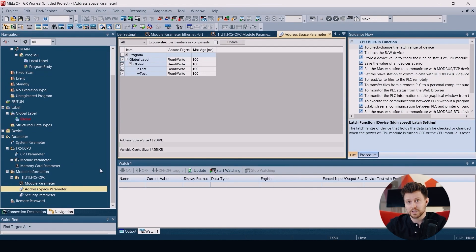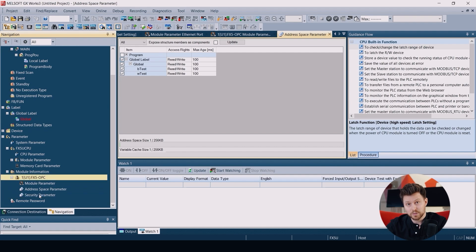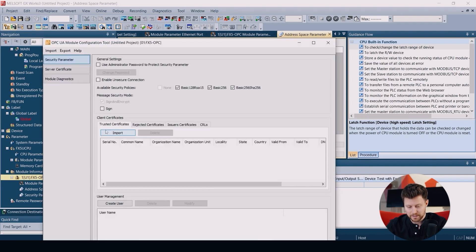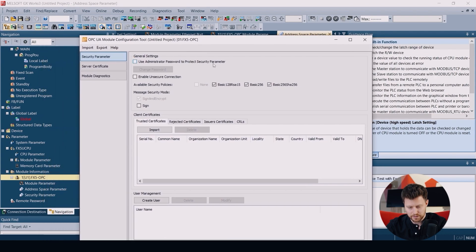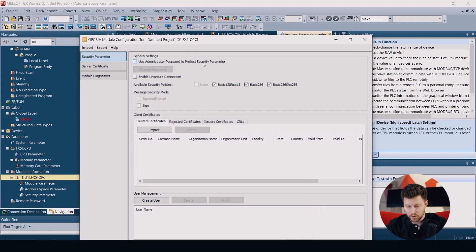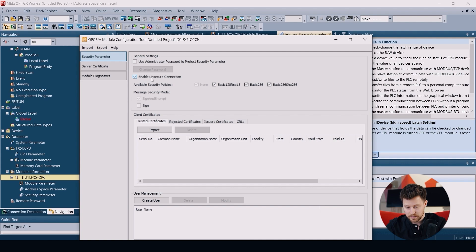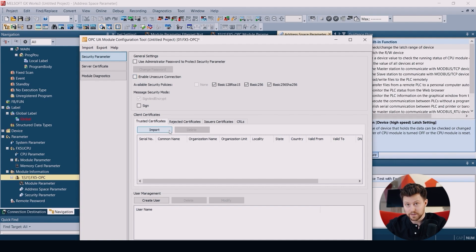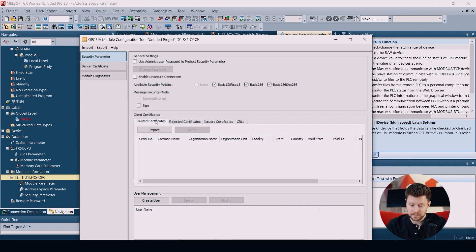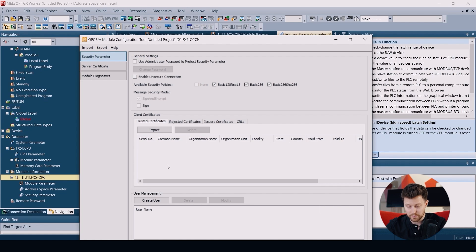Now we can upload our project to PLC. And if the project is already uploaded to our PLC, we go to security parameter in GX Works 3. And here we can choose the security policies of our module. We can, for example, enable the unsecured connection. We can also see the certificates of our clients, so we see trusted and rejected ones. And we have also the user management here.